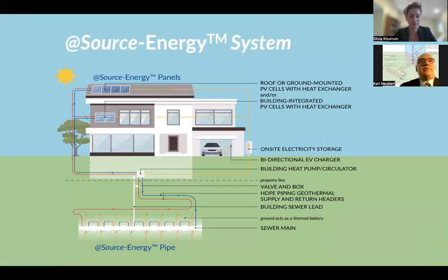The @Source-Energy system has two components that can function standalone or together as a renewable energy system. Below ground, we have the @Source-Energy pipe, which is a precast concrete sewage pipe with a unique HDPE heat exchanger embedded within the walls of the pipe. This low-cost solution allows the entire surface area of a sewage pipe to be used for geo exchange. In other words, we have a thermal battery where we can store and recover energy. Connecting the HDPE heat exchanger between contiguous sections of pipe can form a district heating energy system. During warm weather, heat is moved from a building by a ground source heat pump to the pipe and surrounding ground. During cold weather, heat is recovered from the pipe, its surrounding ground, and the effluent passing through the sewage pipe, and is upgraded by the heat pump within the building.